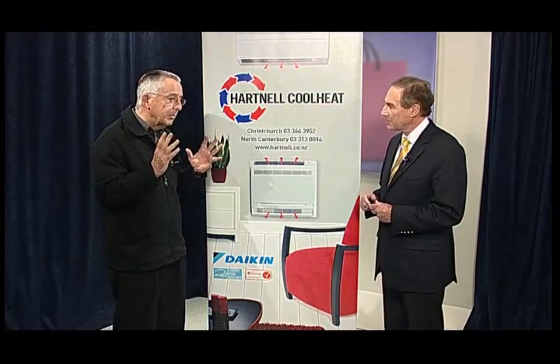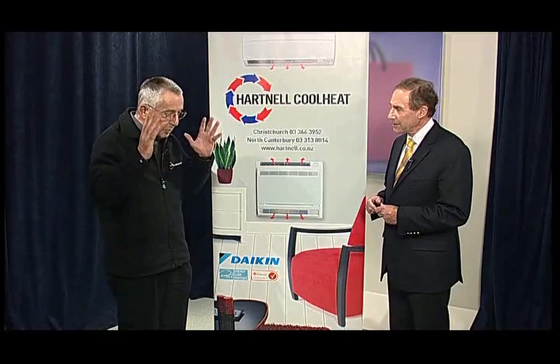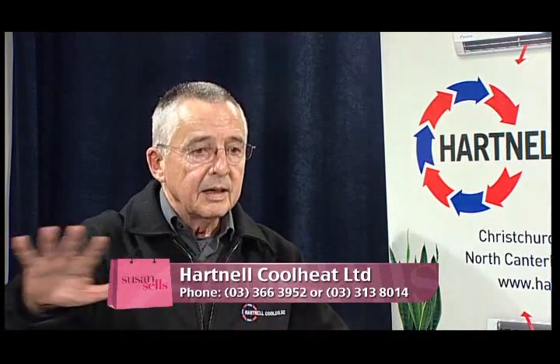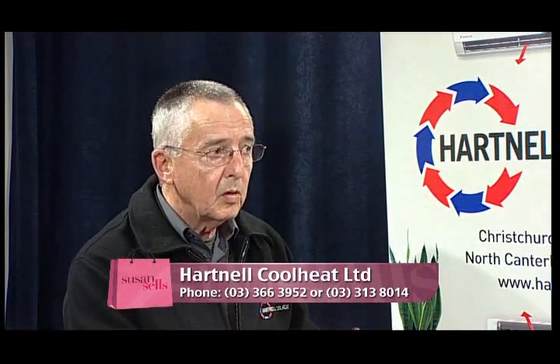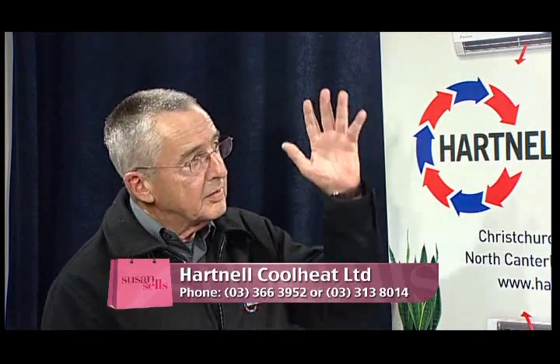Floor unit, yes. And most important, I saw one yesterday where somebody had been in and said a high wall just up here. The guy was a clown because all he's doing is blowing right down onto a settee. You can't have that. You need to put a heat pump in a position where it's blowing, shall we use the expression, into an area of nothing, so that the heat is going, but there is no... You are dealing with moving warm or cold air, which is entirely different from a lot of other forms of heating. So the positioning of the inside unit is absolutely paramount.